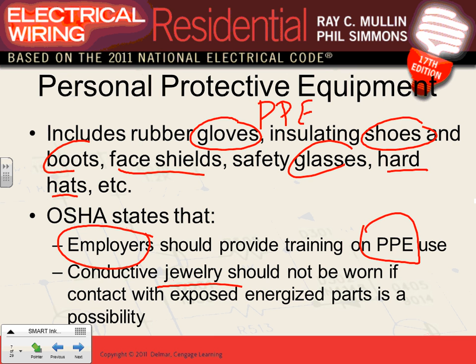When we work on energized objects or equipment, there are 2 hazards. Hazard number 1, electrocution - that's why in 70E, guys, we have the boundaries: limited approach, prohibited approach, and restricted approach. These approaches mean you're supposed to stay, most of them, within 4 feet - you should not be within 4 feet of any open energized equipment because of electrocution risk.